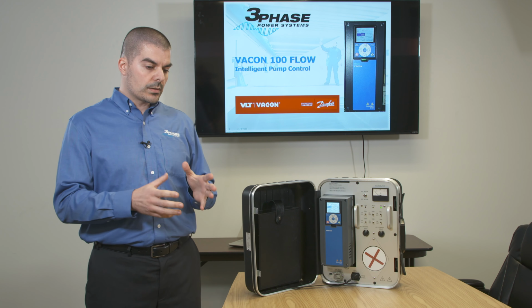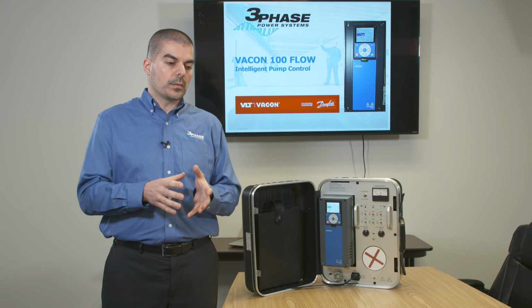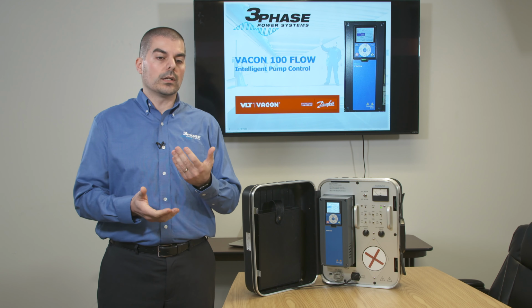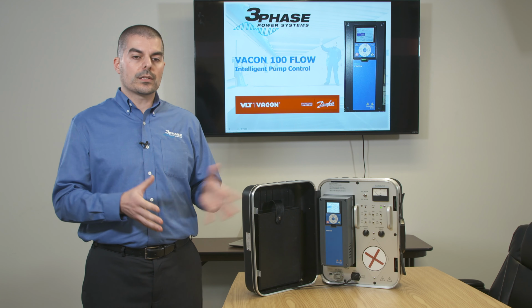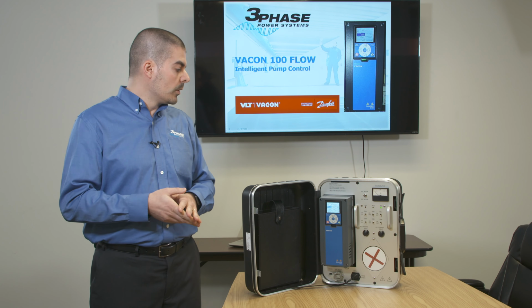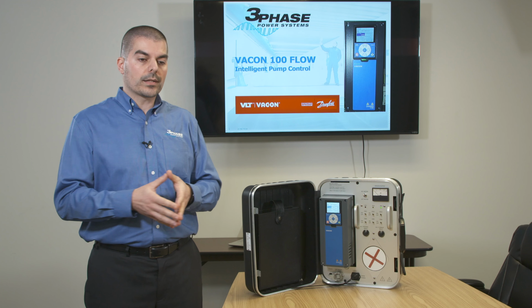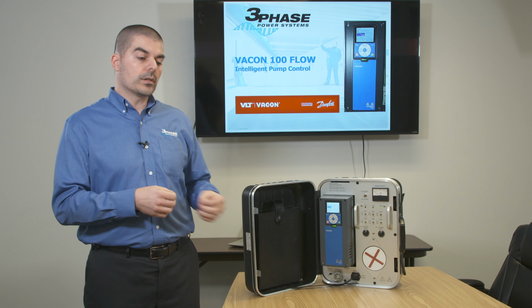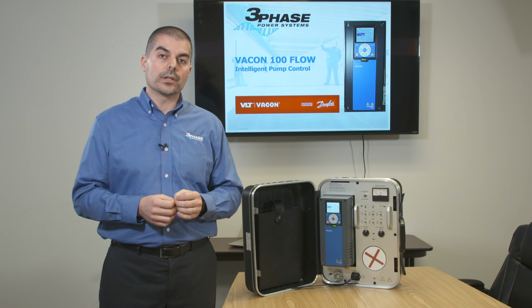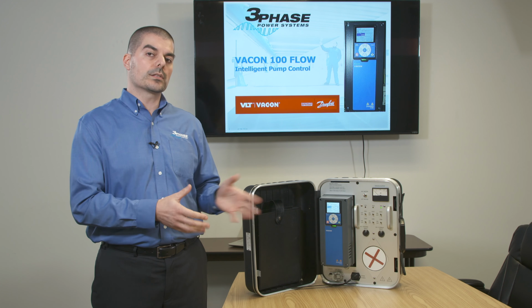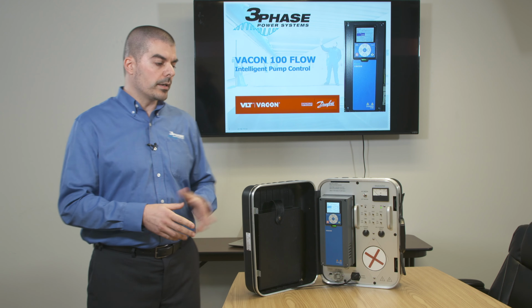So this makes the drive protected against environmental elements, against condensation, and this is one of the other things that makes traditional drives fail, the fact that the boards are not varnished. What others consider an option, VACON and Danfoss considers mandatory and standard. So all of these things come standard with the drive.